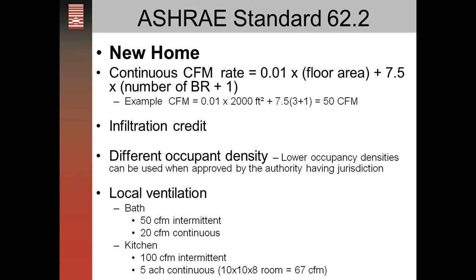The ventilation rate for new homes requires each bathroom to have a 50 CFM intermittent bath fan that can be turned on and off when you'd like, or you could have a 20 CFM continuous fan. You have the option between those two.